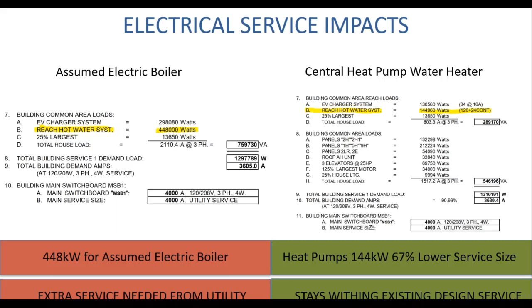One of the things I keep seeing - some of this is based on the REACH code, but some of it is interpretation of the REACH code regarding electric service for EV charging. We have a project now with every parking spot serviced by an electric charging station, and that's a significant load. If these REACH codes require future connections - not just conduit, but actual electric capacity - that's going to be a bigger impact than electrification of the building systems themselves. Bringing that load for every parking space, or 50% of them, is a significant load for vehicles, and it's impacting projects.